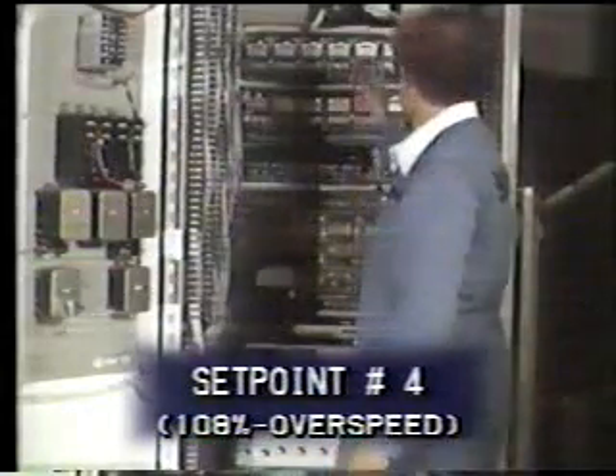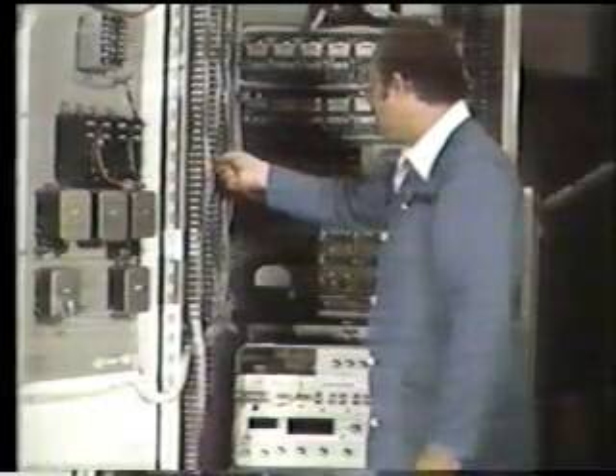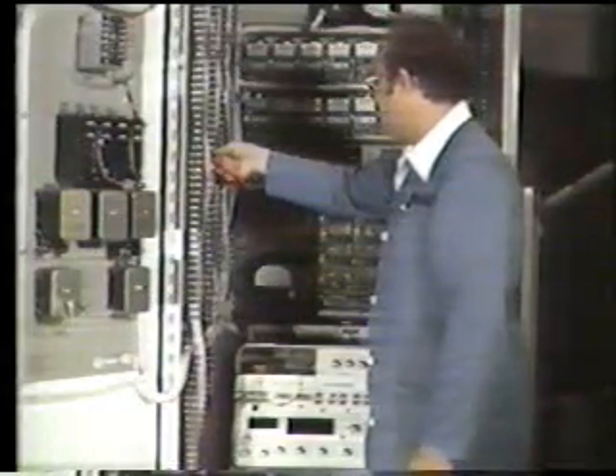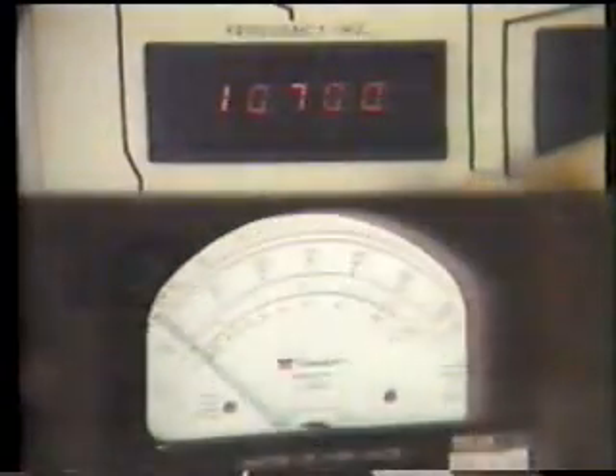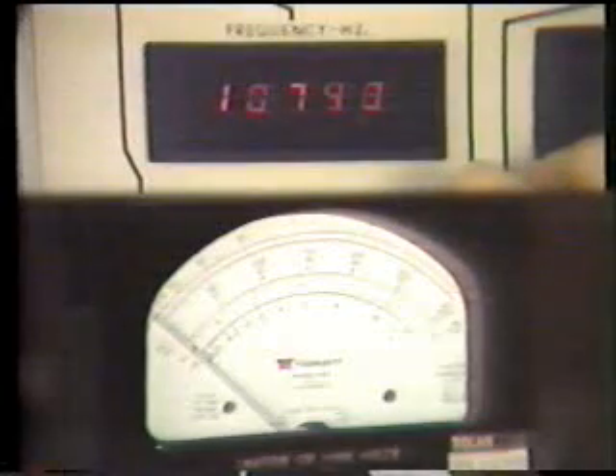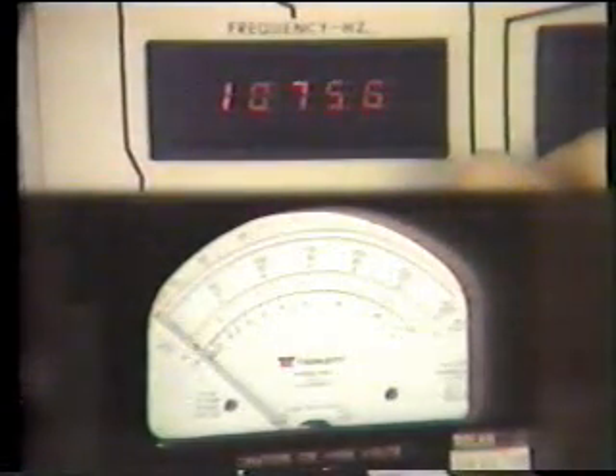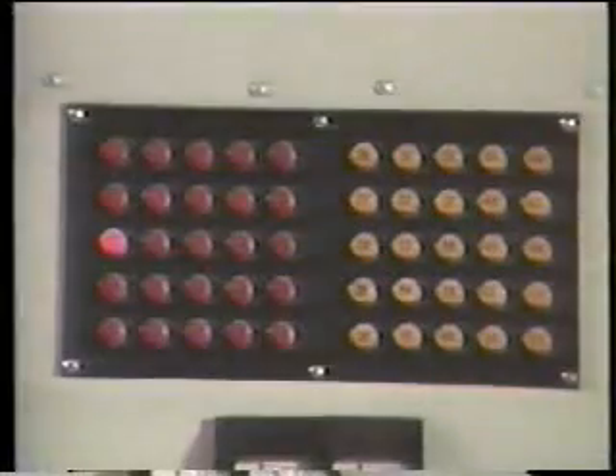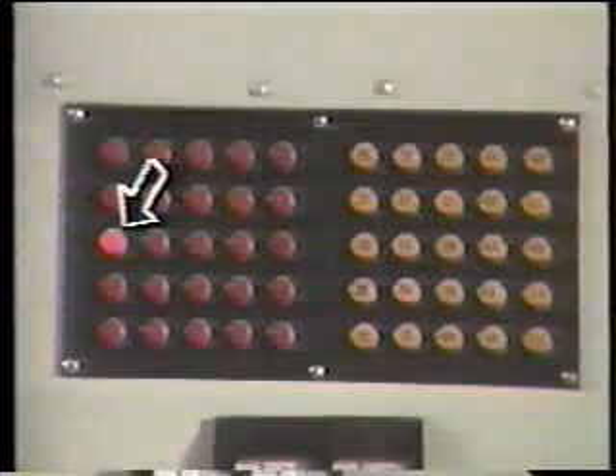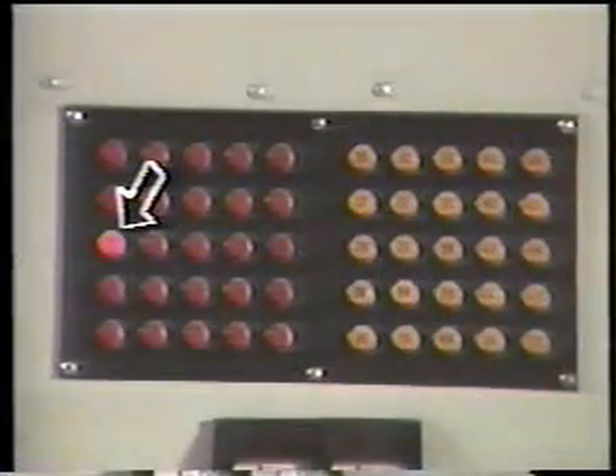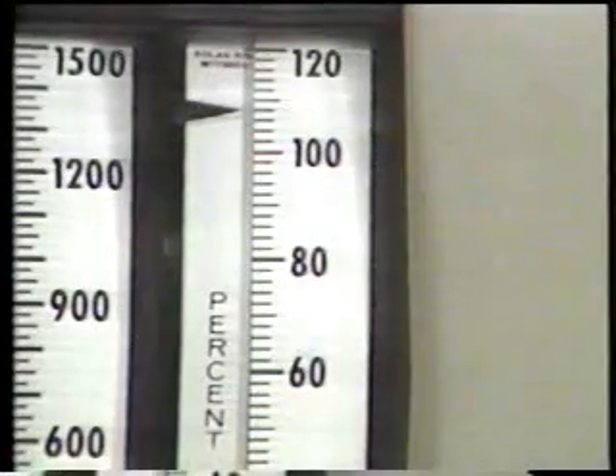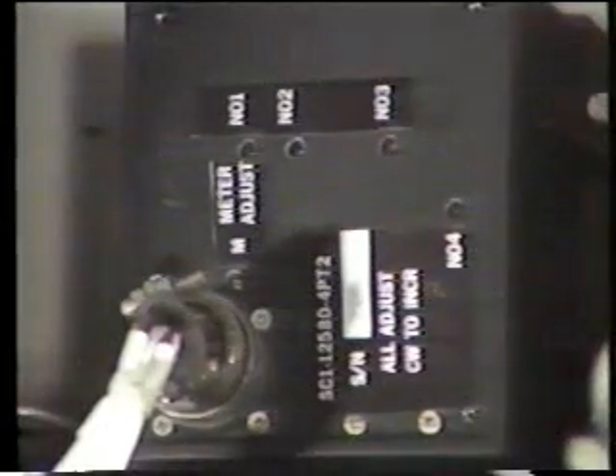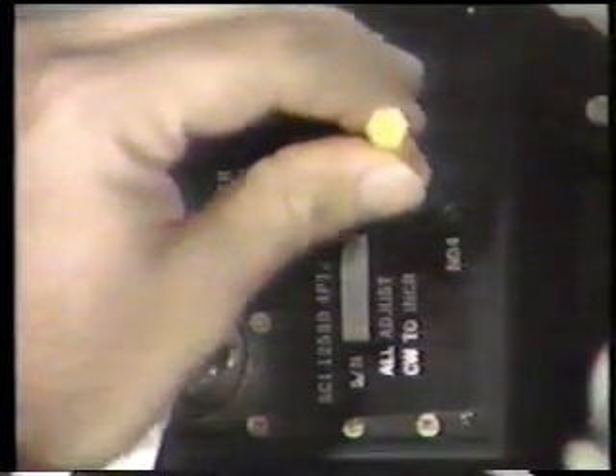Next, verify set point 4, which is the overspeed malfunction set point. Move the voltmeter test leads to the contacts for 108% speed. Slowly increase the frequency output until transfer occurs. Observe the voltmeter for this indication. Note that the malfunction lamp DS3 illuminates at this time. Check the speed meter. It should read 108% speed. If the switch does not transfer at 108% speed, plus or minus 30 Hertz, adjust pot number 4. Recheck set point after each adjustment.